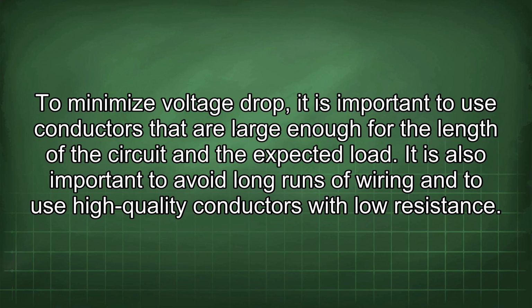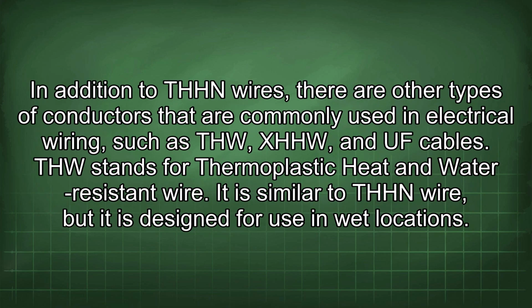To minimize voltage drop, it is important to use conductors that are large enough for the length of the circuit and the expected load. It is also important to avoid long runs of wiring and to use high-quality conductors with low resistance. In addition to THHN wires, there are other types of conductors commonly used, such as THW, XHHW, and UF cables.